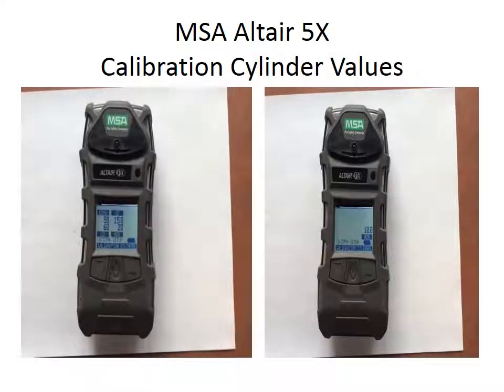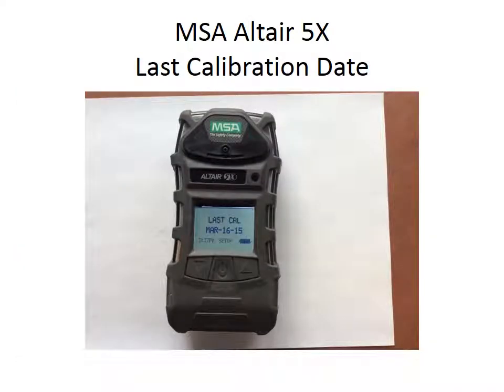The calibration cylinder values is the next screen you're going to see, and you can see for the different sensors the optimum level that it needs to read from that calibration cylinder when it goes through calibration. So you can see what those levels are for all the different readings. Next screen that comes up is the last calibration date, and you can see here that when this picture was taken, the last calibration was on March 16th, 2015. And if you look at the little battery icon to the right, there's a little check mark, and that just tells you that it was a successful calibration.